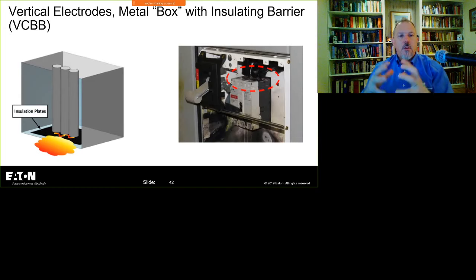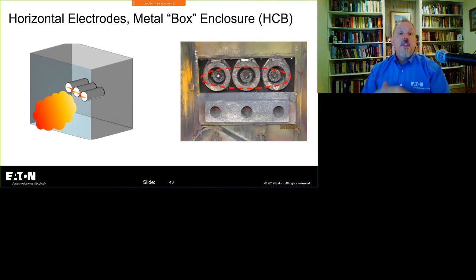Now, when you have a vertical electrode with a metal box with an insulating barrier, that's when you get down towards the end of that bus or the conductor, the energized part, where it's close to an insulated plate or whatnot. For the most part, VCB is what you would use. I believe the worst case is VCBB, which I would just default to. Difference isn't that much. Then you have horizontal.